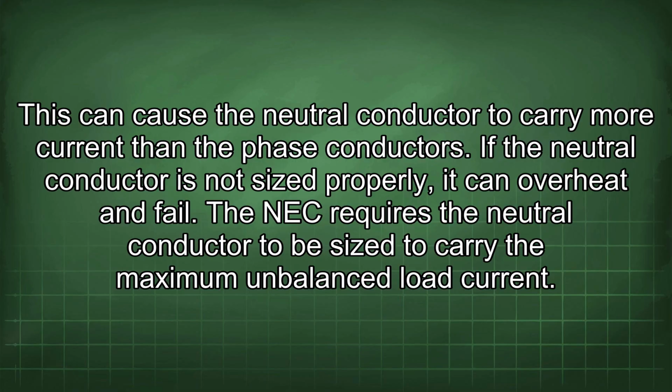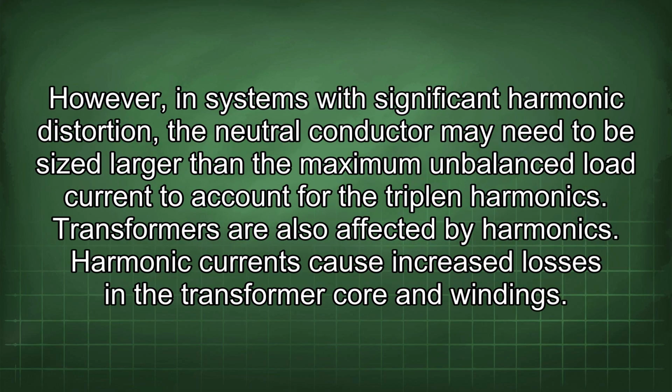The NEC requires the neutral conductor to be sized to carry the maximum unbalanced load current. However, in systems with significant harmonic distortion, the neutral conductor may need to be sized larger than the maximum unbalanced load current to account for the triplen harmonics.